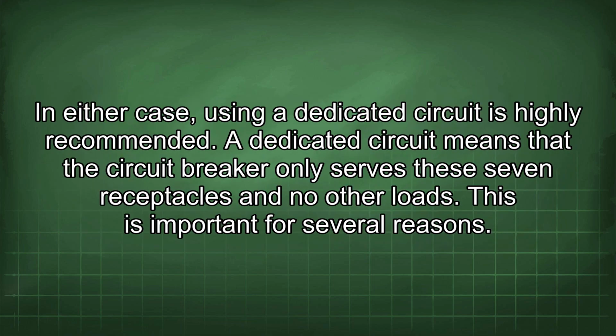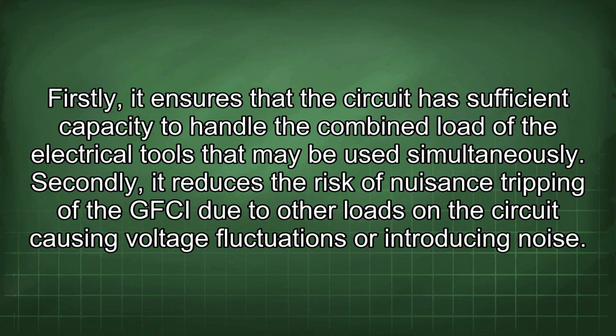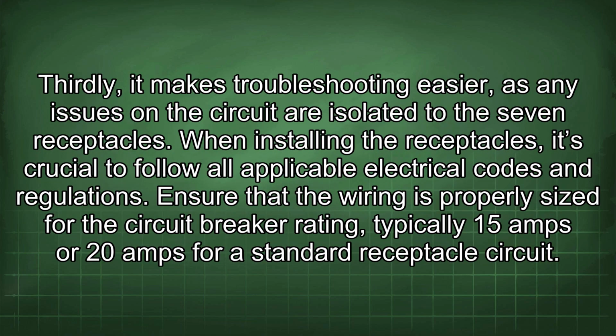In either case, using a dedicated circuit is highly recommended. A dedicated circuit means that the circuit breaker only serves these 7 receptacles and no other loads. This is important for several reasons. Firstly, it ensures that the circuit has sufficient capacity to handle the combined load of the electrical tools that may be used simultaneously. Secondly, it reduces the risk of nuisance tripping of the GFCI due to other loads on the circuit, causing voltage fluctuations or introducing noise. Thirdly, it makes troubleshooting easier, as any issues in the circuit are isolated to the 7 receptacles.